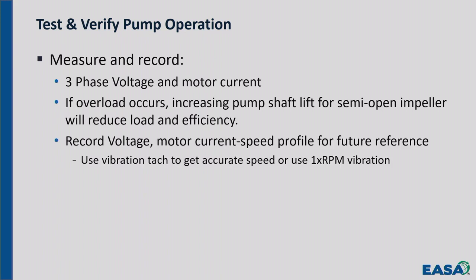You want to record the speed, current, voltage profile. So if they're going to change it, they're going to be run through a series of different loads on this pump, opening and closing it. You want to know what the voltage was, what the current was, and what the rotor speed was. And you want to document that. Come back later, and you think you've got an open rotor in the motor. You can check to see if your speed, current, voltage profile has changed, which would be a key indication of rotor problems. Okay? And you can use your vibration analyzer as a tachometer, usually.